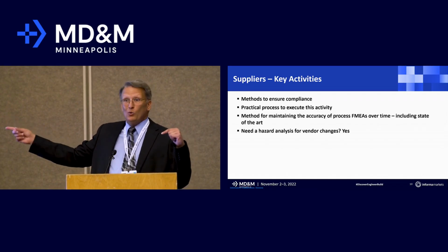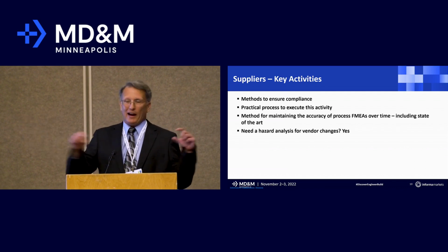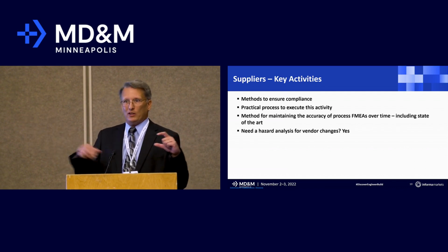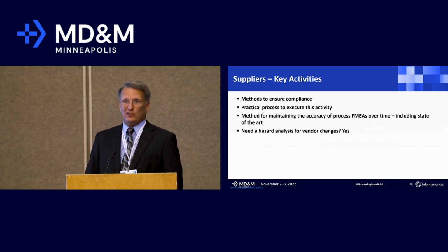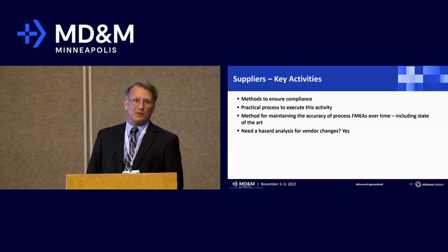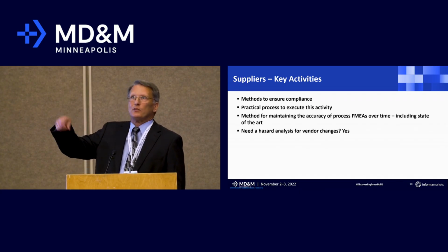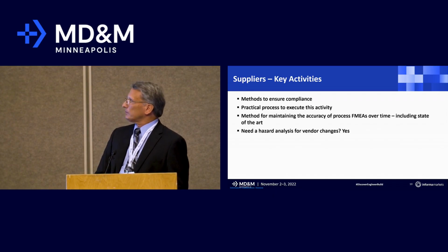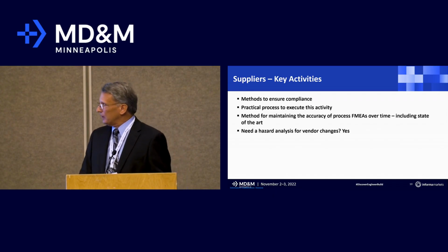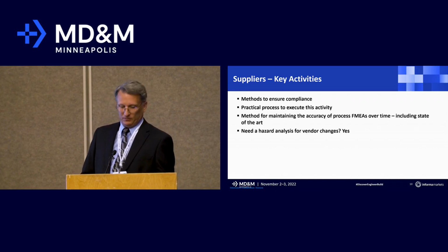So do you need a new one is a different question. But if you've already done a good hazard analysis, then you go back and say which line this change fits under and why it's no big deal, then it's already done. And if you can't, if it's not an easy answer, well, then obviously you need to add line 18 to your risk management documentation, because this is something where a change has happened that triggers new risks, and so on. That's all in the standard. So I think the simple answer to, do you need a hazard analysis for vendor changes? The simple answer is yes.